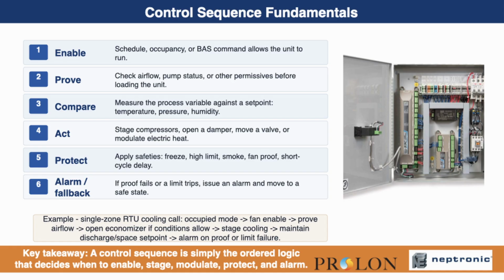A control sequence is simply the logic that determines how the system operates. In most HVAC applications, the sequence follows a recognizable pattern. First, the unit is enabled based on schedule, occupancy, or a command. Then the controller decides whether the unit needs heating, cooling, ventilation, or humidity control. After that, it stages or modulates outputs to meet the load. Throughout that process, it also checks safeties and proving conditions, and it generates alarms when something is outside expected operation.